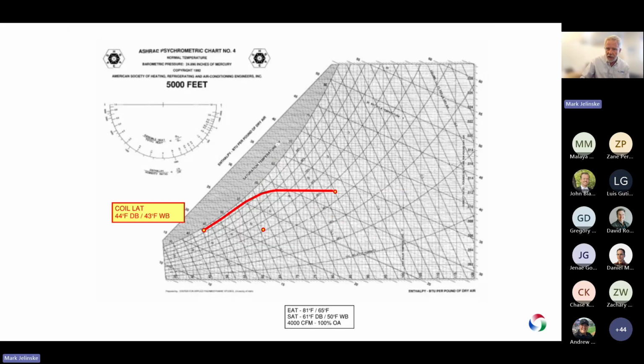All right, so we know we need to lower the humidity ratio below the desired supply air humidity ratio. And we were told a desired leaving design condition is down here on the psych chart. So we've got to cool down to at least that. And we know that it's going to be about saturated. So it's going to end up in this condition, 44-degree dry bulb, 43-degree wet bulb, which gets us below the desired absolute humidity.